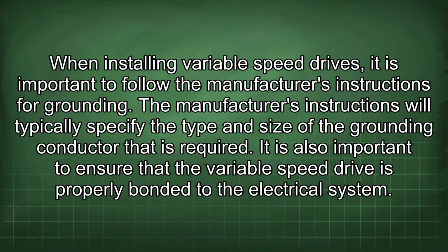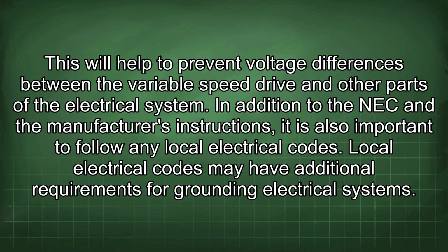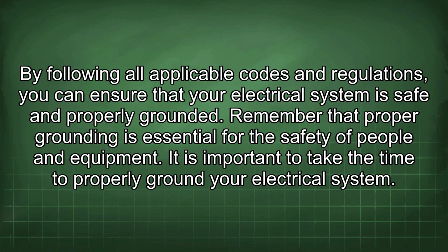When installing variable speed drives, it is important to follow the manufacturer's instructions for grounding. The manufacturer's instructions will typically specify the type and size of the grounding conductor that is required. It is also important to ensure that the variable speed drive is properly bonded to the electrical system. This will help to prevent voltage differences between the variable speed drive and other parts of the electrical system. In addition to the NEC and the manufacturer's instructions, it is also important to follow any local electrical codes. Local electrical codes may have additional requirements for grounding electrical systems. By following all applicable codes and regulations, you can ensure that your electrical system is safe and properly grounded.